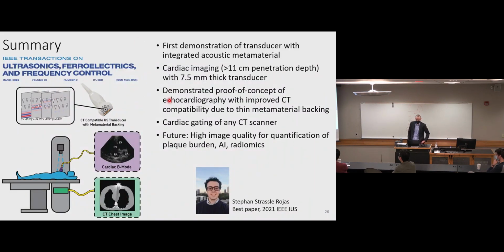So to summarize this part, we think that this is the first demonstration of a transducer that contains, as part of it, an integrated acoustic diode or metamaterial. We've shown that we can do in vivo cardiac imaging in an adult with a penetration depth greater than 11 centimeters using that device. And definitely this thinner transducer is not paper thin, right? It's still 7.5 millimeters. And most of that thickness or that volume is still the thickness of the acoustic backing. Only about 1 millimeter is everything else. Because we still have an acoustically lossy backing, we just have less of it to make it more CT compatible.